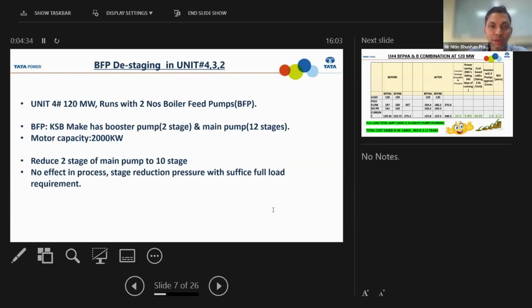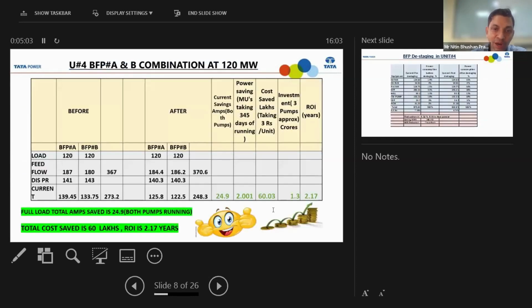This is our project that we have taken in various units, Unit 4, Unit 3, and Unit 2. That is the de-staging of boiler feed pumps. The boiler feed pump is the main heart of the plant and supplies water to the boiler. In JOJOBERA, we have a boiler feed pump of 12 stages, and in this we have reduced 2 stages. The motor capacity is 2000 kilowatt, and at full load condition we have achieved a reduction of around 12.5 amperes at 6.6 kV.